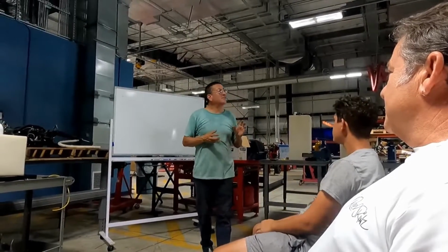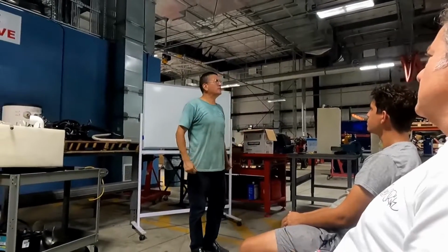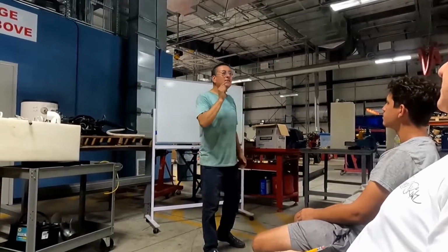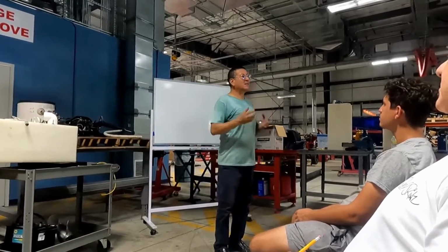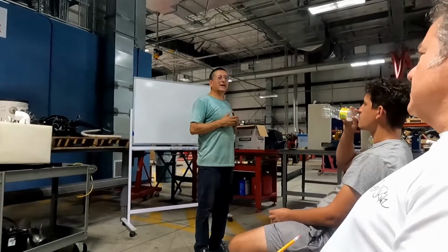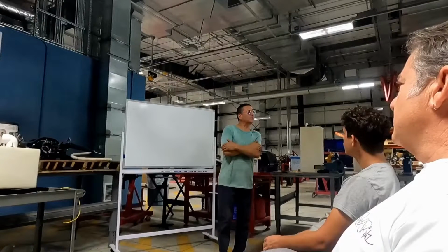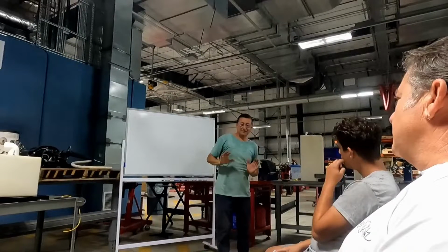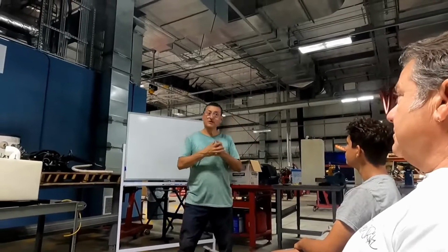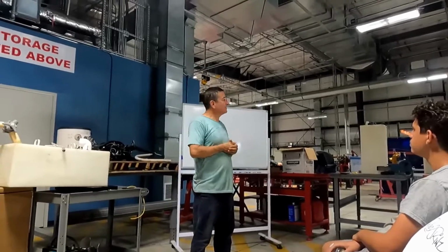And they say, you can let that fuel sit for 1 day and the water is not separated. This is an indication that it's a good fuel, because they added additives, and the additives keep the water emulsified with the fuel. And they said, show me the water separated. Where is the water? And you let it sit, no water separated. Probably it's good fuel. No. It's fuel emulsified with water because they added additives. That's not good.